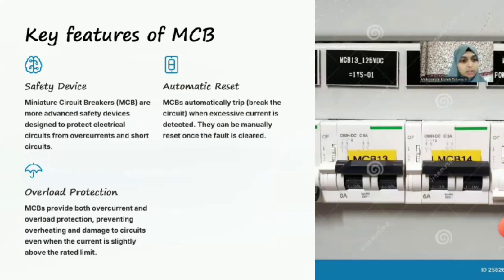Application: it is used in domestic, commercial and industrial purposes because of these key features like safety device. Miniature circuit breaker is a more advanced safety device compared to the other devices. And automatic reset, it can be automatically tripped when the excessive current is detected. And overload protection, as we have seen in the SFU, SFU and MCB have the common point that they can handle the overload protection.